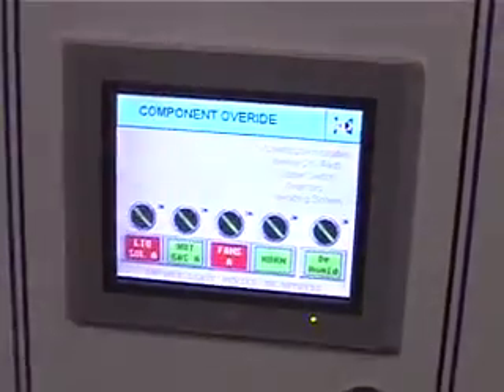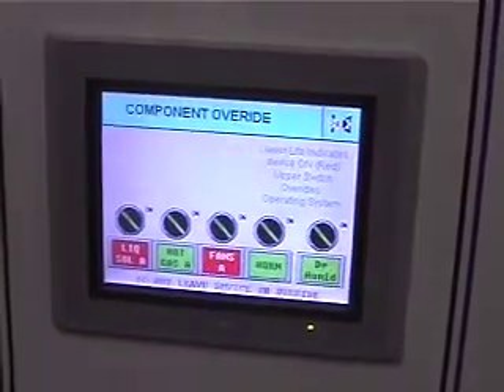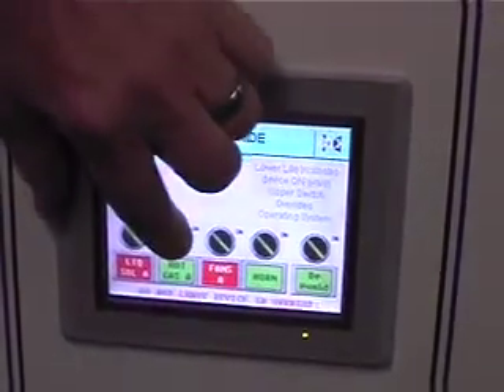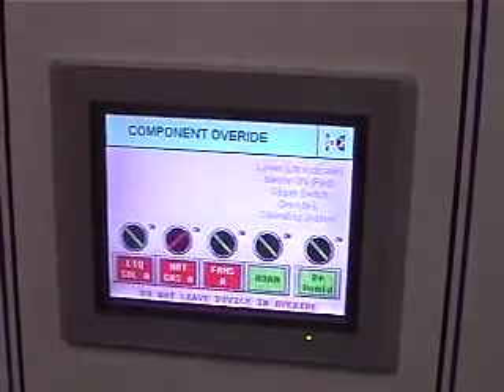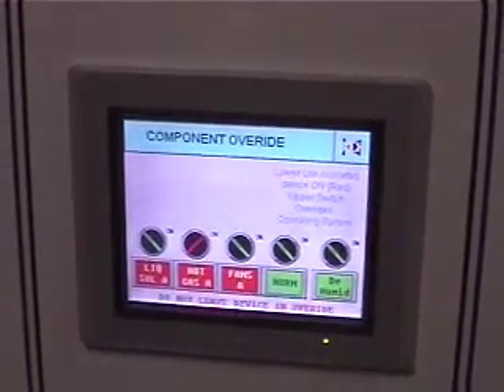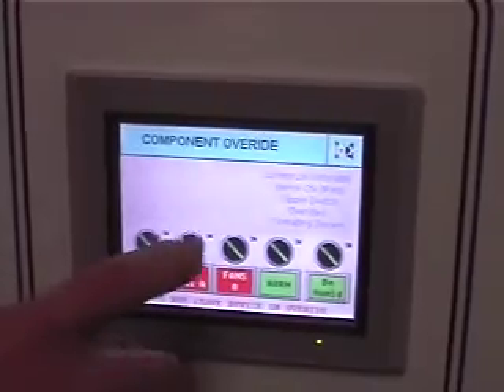What we did is we gave this the ability to override that. And now we have all kinds of stuff that says don't leave it in override. But if we wanted a hot gas valve to open, that little switch you heard, the hot gas valve opened. Okay? Notice it stays red. Now that thing will stay. You can leave this and that thing will stay just like it is.